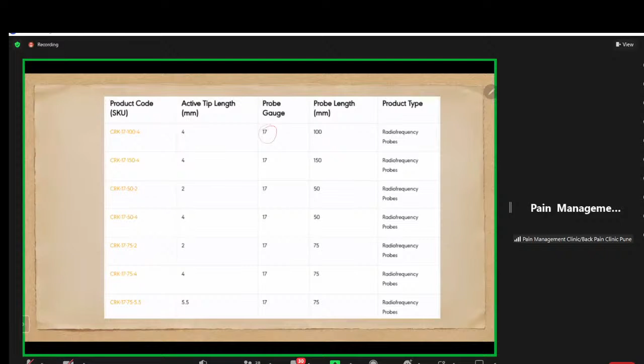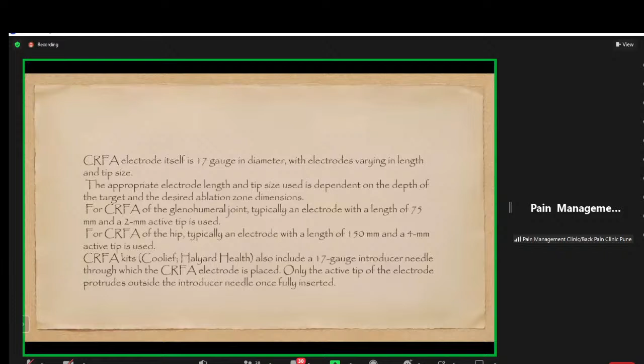The electrode itself is 17 gauge in diameter, with the electrode varying in length and tip. Depending on which tissue we want to target, we have to choose the size of the needle. The appropriate electrode length and tip size depend on the depth of the target and the desired ablation zone dimension. For cooled radiofrequency ablation of the glenohumeral joint, typically an electrode with a length of 75 mm with a 2 mm active tip is used. For the hip, typically the electrode is 150 mm with a 4 mm active tip. And in the SI joint, I use the 7.5 with a 4 mm active tip.